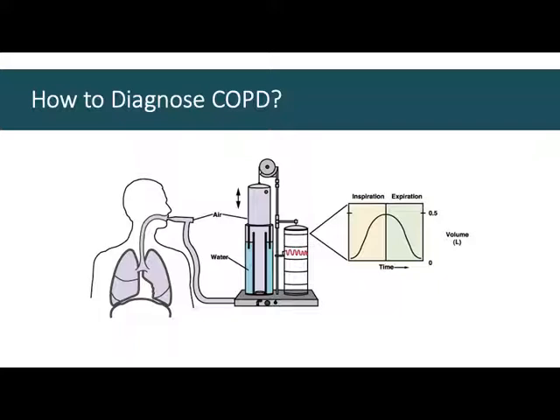One of the ways to assess lung function is the bell spirometer. This is what you would use to measure static lung volume. Here you have a person whose lungs are essentially continuous with the spirometer — a closed system. When they breathe in, they breathe in air from inside the bell. Air goes in, the bell drops. Because this is on a pulley, the bell dropping means the pen on the rotating drum moves upwards and draws a line.